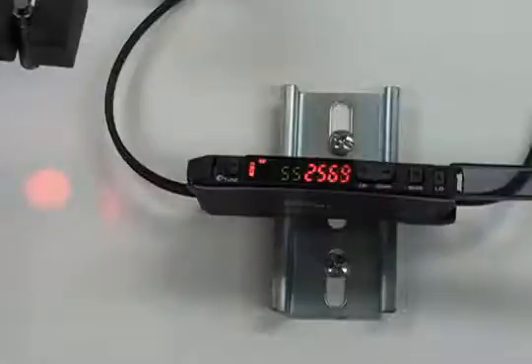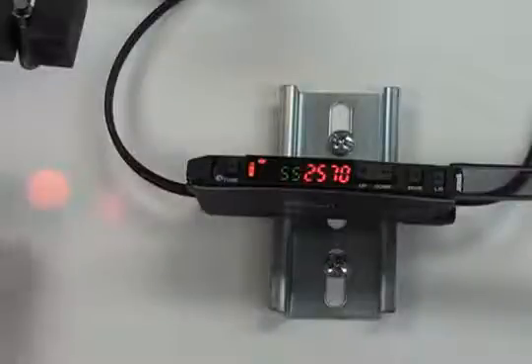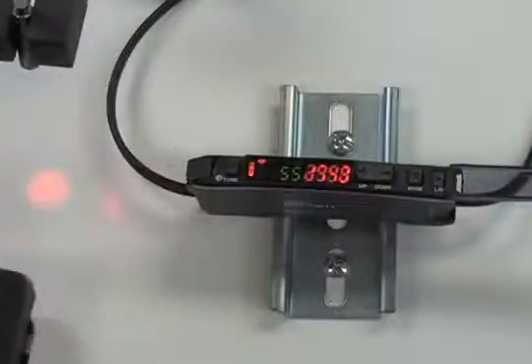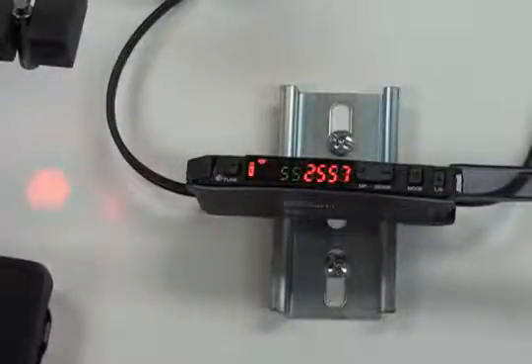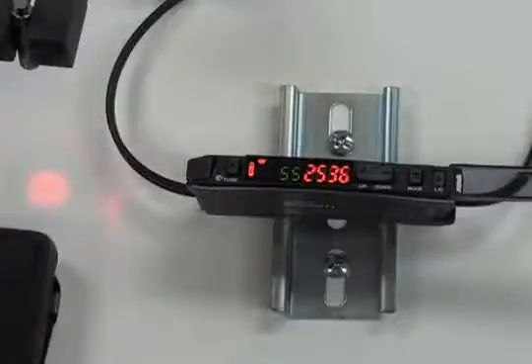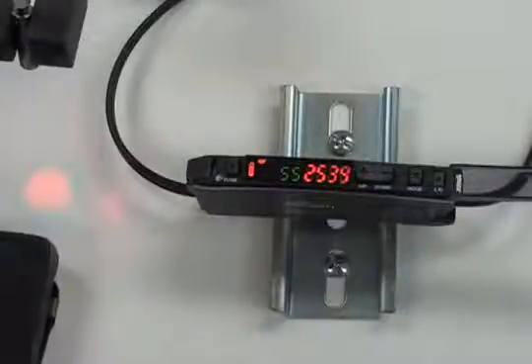Let's take a look at the basic calibration of the E3X HD amplifier. Because this is a lighter background, I'm actually going to use a dark surface target, so there's a significant difference between the two, because this is a light intensity based sensor.